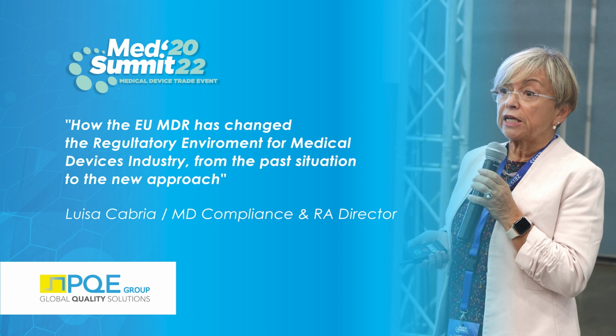UDI is made of 3 parts. A basic UDI that identifies the family of the product. That means a group of products having the same intended use and that are covered by the same CE mark and by the same technical file. Then you have the UDI-DI. The UDI-DI identifies the model, it is exactly the same as your SKU, for instance.